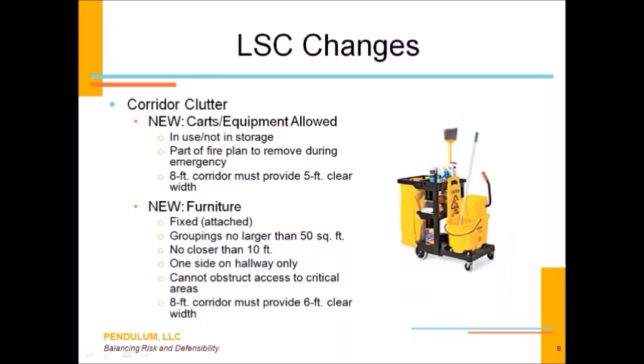When it comes to other items like corridor clutter, NFPA 101, the Life Safety Code, allows for some new conditions to be present within that means of egress. And again, when we talk about the minimal means of egress, we're talking about those 8-foot corridors. In an 8-foot corridor, you are now allowed to have the presence of equipment, things like carts and other items that you need to operate your facility, present for an unlimited amount of time, providing that you are leaving a residual 5-foot clear width within that minimal 8-foot means of egress.